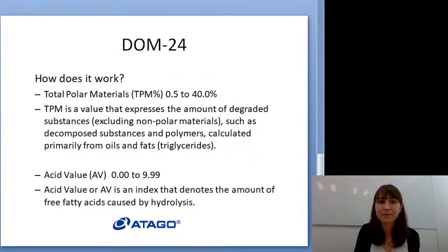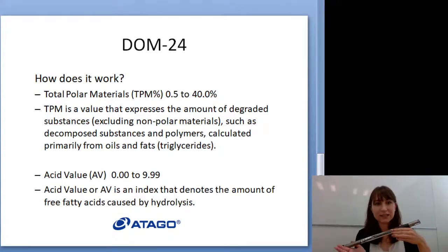Okay, so DOM-24, let's talk about how it works in case you are curious about the scale and what number you need to get. DOM-24 is a type of conductivity meter, but a little bit different than some other ATAGO products that you might be familiar with. It measures the total polar materials in the oil, and that's denoted by TPM percent. So it will measure from 0.5 TPM up to 40.0% TPM.